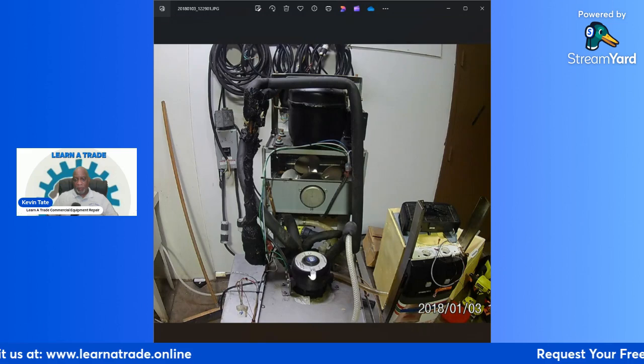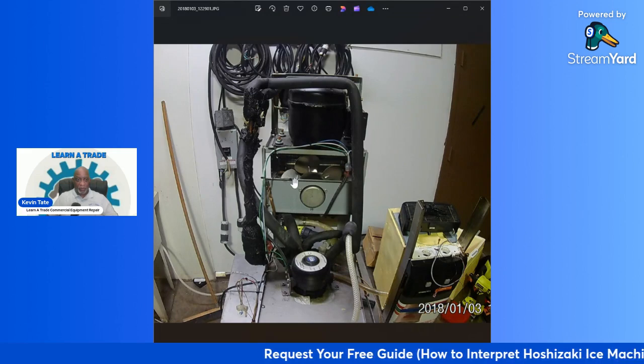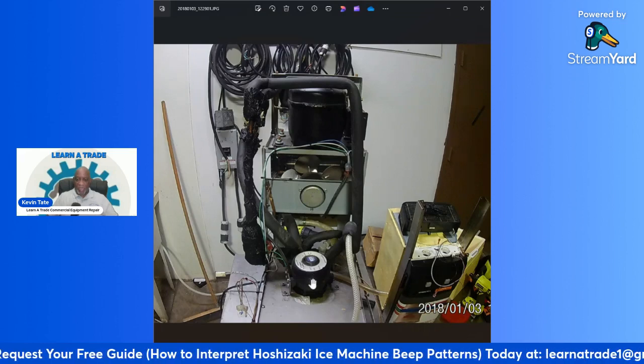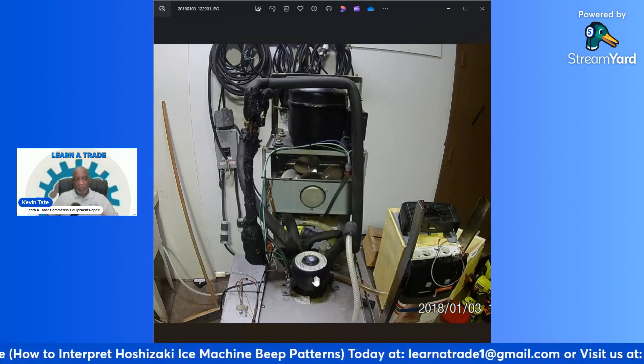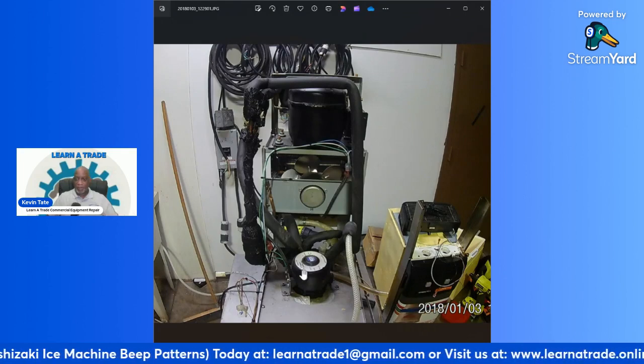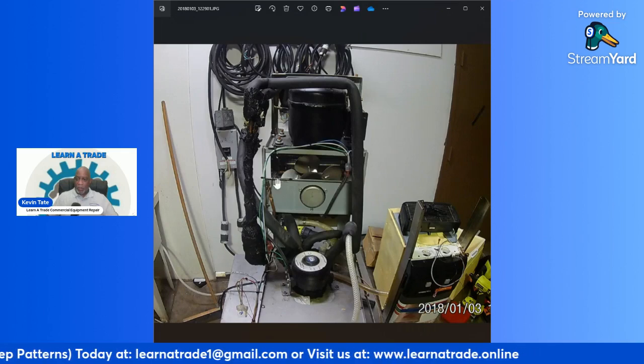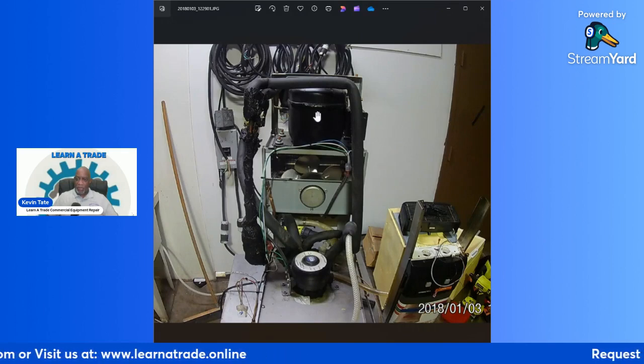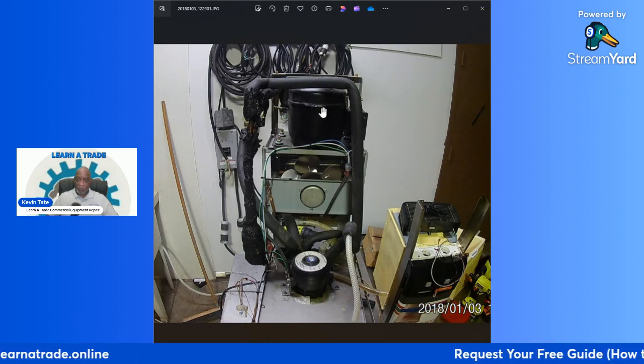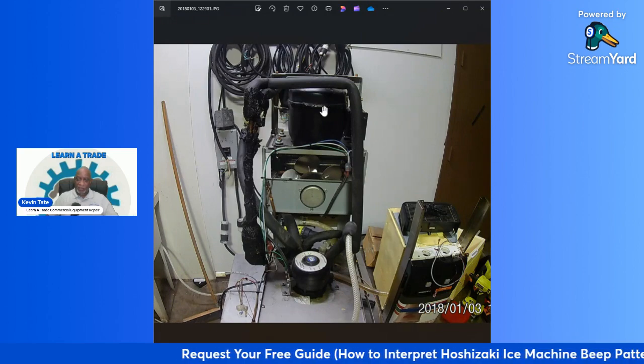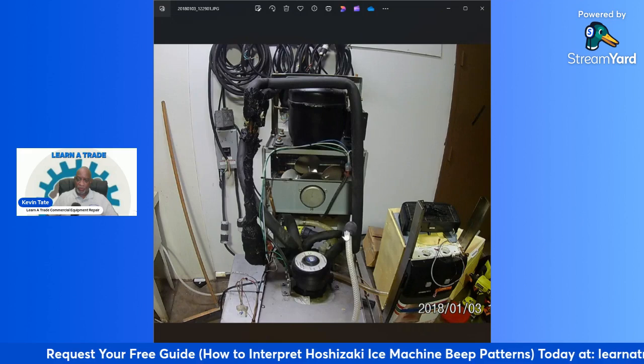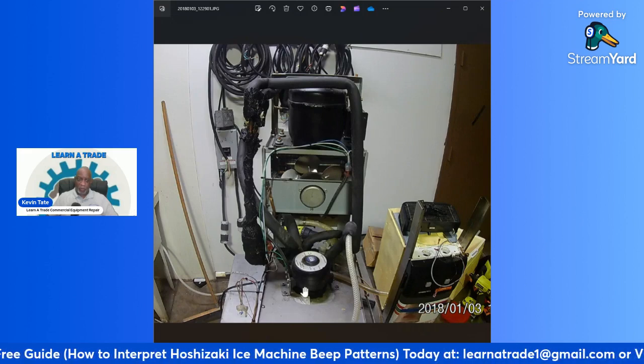Once I remove all of the refrigeration portion of the machine, I'll have access to this and can go ahead and replace it with the new one. Right here you can see the condenser fan, the condenser, and the compressor. These are the low side and high side lines for the refrigerant, and the refrigerant is all running into this water bath.